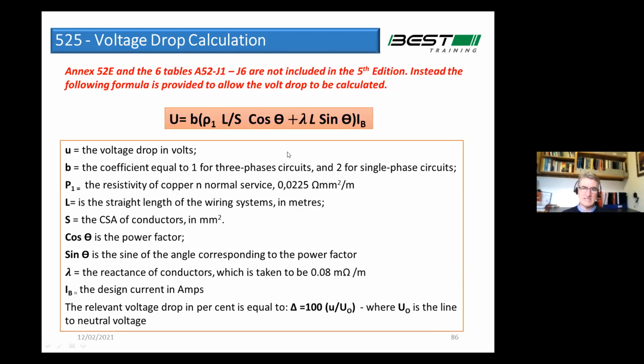It looks at the resistivity of copper and the reactance of a typical low voltage cable. And you have to know your cosine, your power factor, and use the cosine, and then get the sine of the angle. Blah, blah, blah. It's very complicated. It does work. You put it into Excel, but be very careful when you're using it for three-phase voltage drop calculations. Your answer comes out in phase voltage, okay? So you need to convert it back. You need to multiply back. And there's a bit of argument, a big academic discussion about that at the moment.